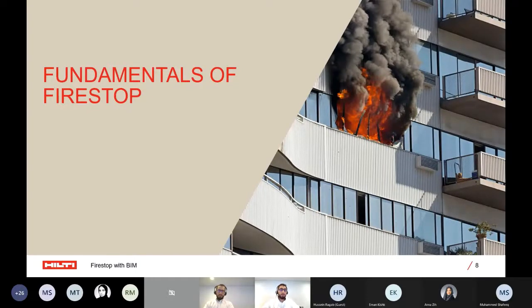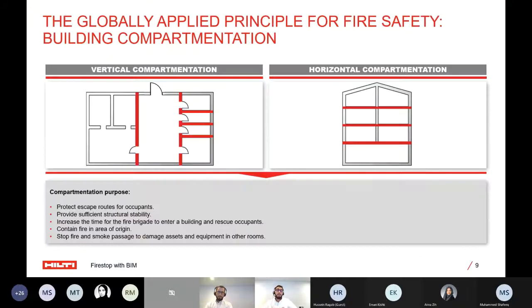Let's talk about the fundamentals of Firestop. The main, global principle that Firestop follows is called compartmentation. As we saw in the previous video, compartmentation means that if a fire happens in a certain room, we want to make sure it stays in that room and doesn't spread to adjacent or other locations. This gives enough time for people to evacuate, and enough time for the fire department or civil defense to come and control the fire. This is what you may be familiar with as fire-rated zones or fire zones.